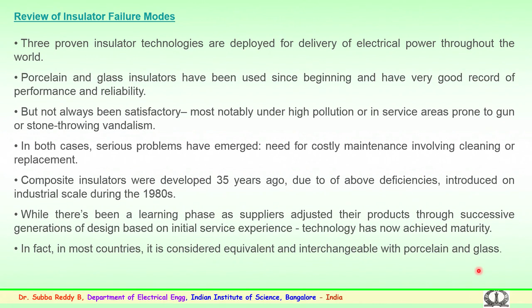So, now looking into the various failure modes which have happened over the period for all the technologies, we have seen the failure in case of a mechanical separation, that is the insulator string getting detached from the tower or from the conductor. The service experience has indicated that toughened glass strings fail significantly less in comparison to the porcelain or composite insulators. So, the performance of glass insulators, particularly for mechanical separation, has been better than other technologies.